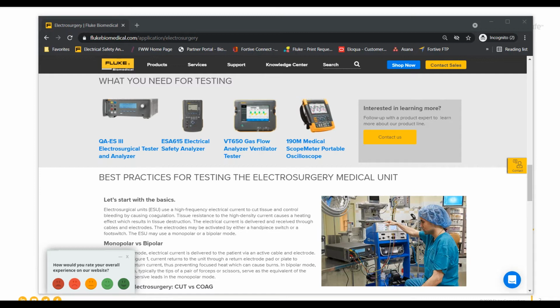You know, if you find something wrong with your QA or with your ESU, you might need to get in and see what that waveform is. What is the energy output? A nice feature about the QA-ES III is on the back of it, we actually have a port that can connect straight to your 190M scope meter, and you can see that output waveform of the ESU that you're analyzing. And believe it or not, that's actually listed in some of the service manuals. So again, if you haven't opened up your ESU service manual in a while, maybe thumb through it real quick and make sure there's not a test that you're missing, and you didn't even know that you could do it because of all these great products.